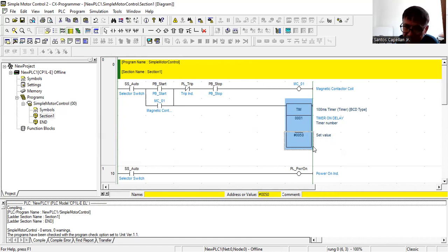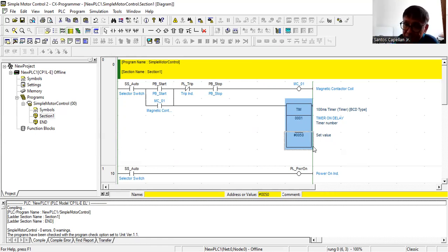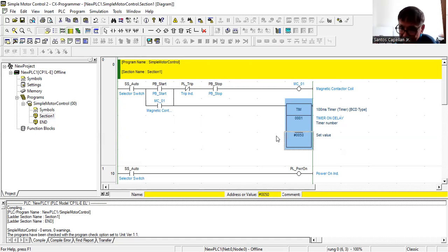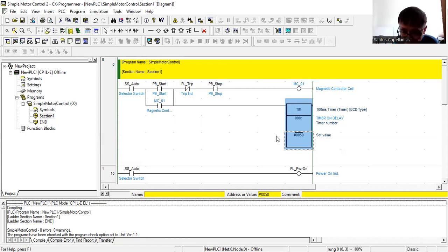This is in milliseconds. In your Y-Delta control you will be using a timer. When the timer is energized, your Star contactor will run with the main contactor first, then after the set value the main and delta contactors will be energized. That is why Y-Delta is called reduced-voltage starting.